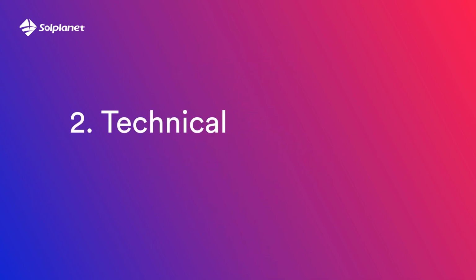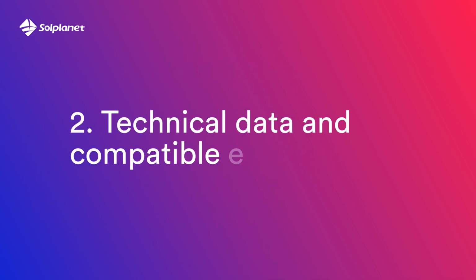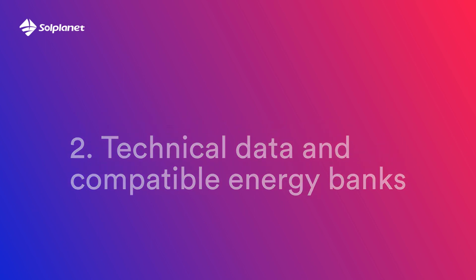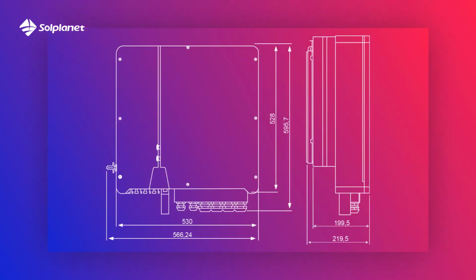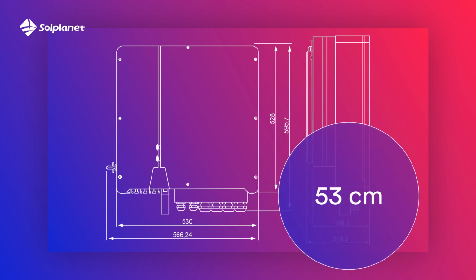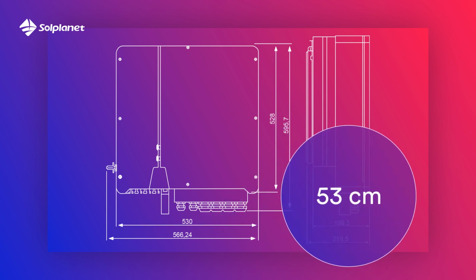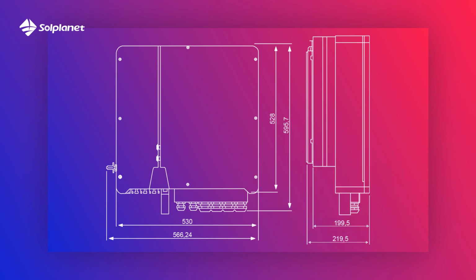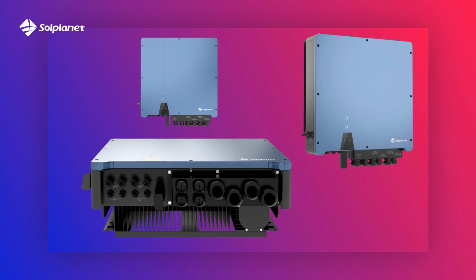Point 2. Technical data and compatible energy banks. Here you can see the dimensions of hybrid inverter. Width and height is about 53 cm. As you can see, the inverter is not too big and looks excellent. Now you can see technical data. These inverters you can oversize by 50% on the DC side.